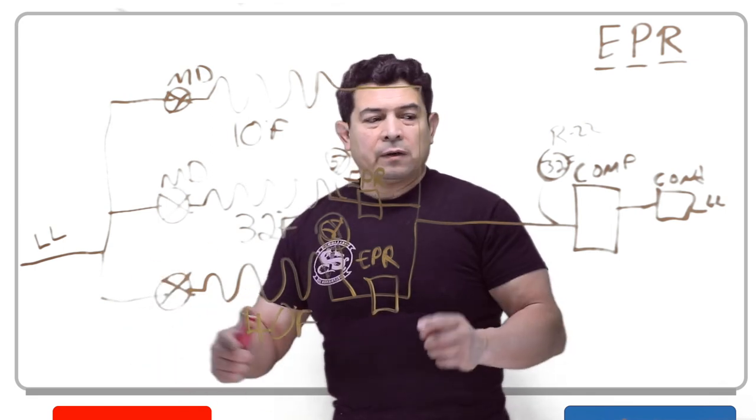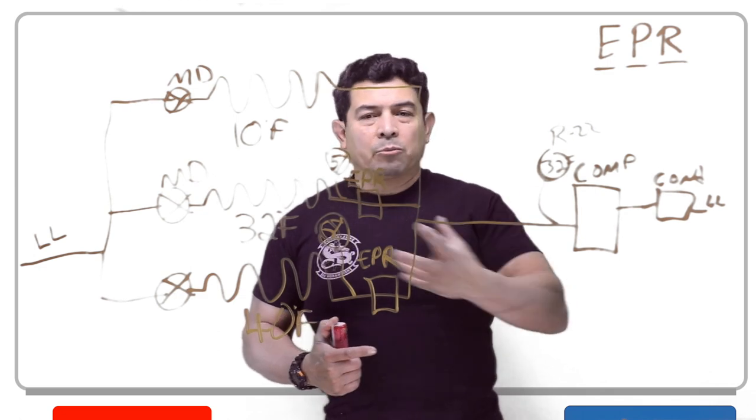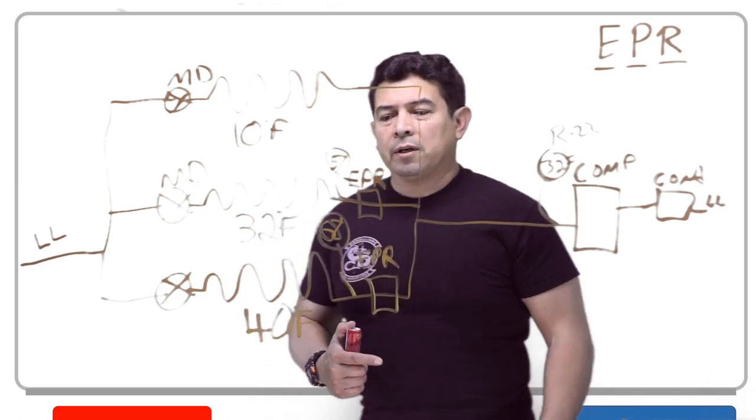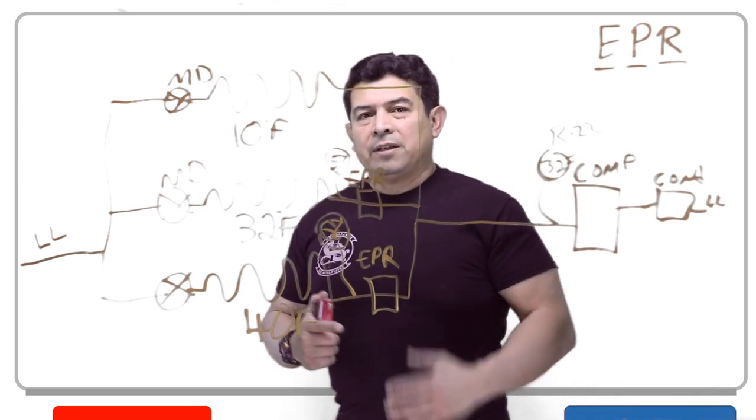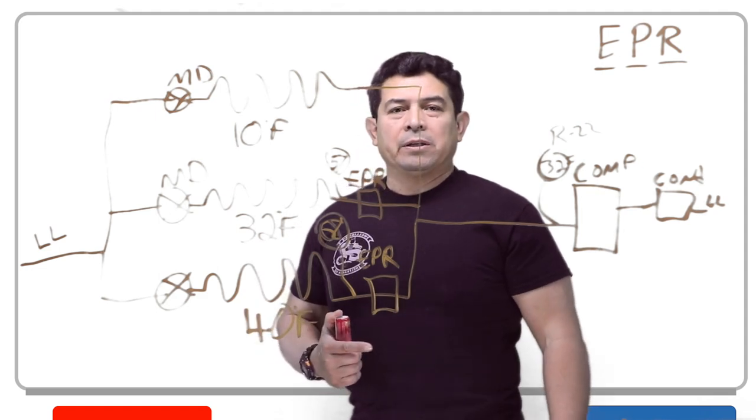We could actually add another one here as long as the compressor can handle the load. As long as this compressor can handle all that refrigerant, yes, we can keep adding more. So this is an example of how the EPR valve works, where you may see it, and how they are used.